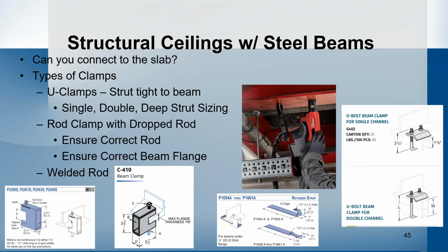We also see these often required because the C-type clamps on the bottom left there aren't necessarily permitted, because the EOR doesn't want there to be any kind of offset loading on the flange. So they want to limit the amount that you would be pulling on a single flange. When you're designing those C-type clamps though, you need to make sure that you're looking at the actual beam size, because the flange size of the steel beam is going to affect what type of clamp is permitted.